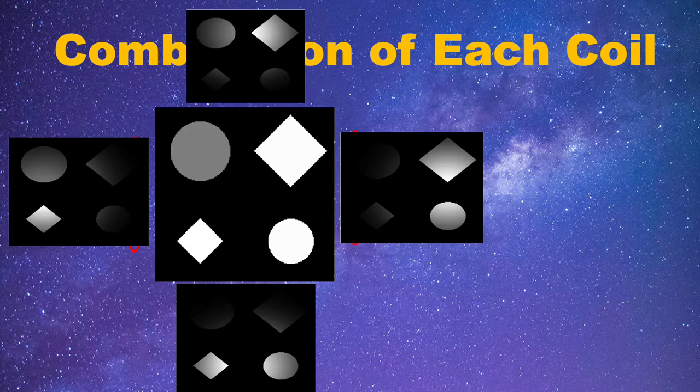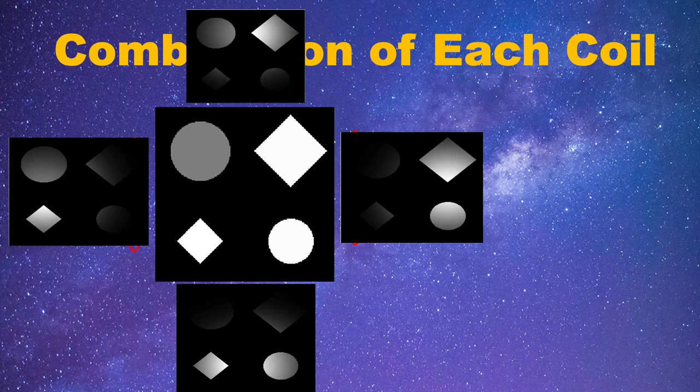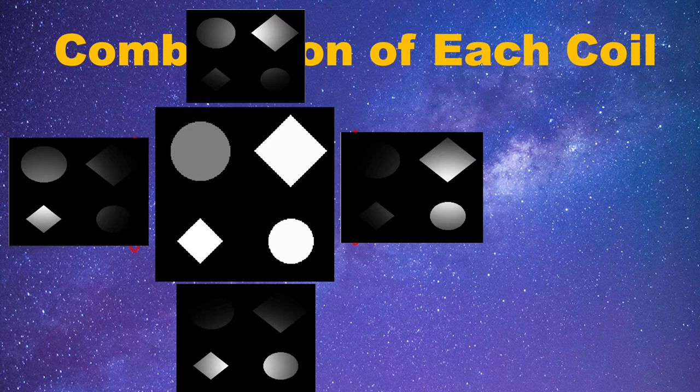Notice that some images are bright on one side and dark in the others. This is because different coils are located in different positions relative to the object, and each of the coils has its effective detecting field. It's just like you take a picture of a person from different side and you will get a different view.